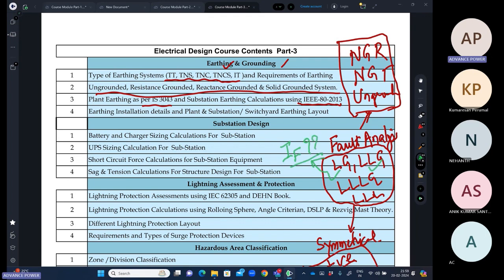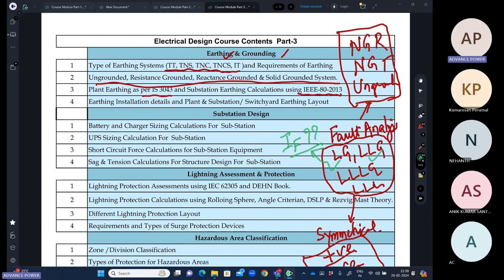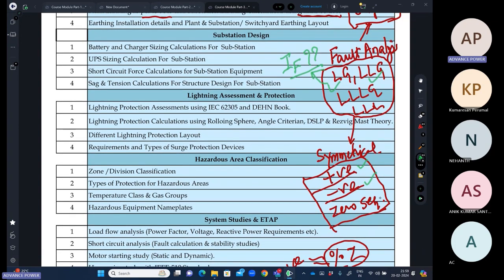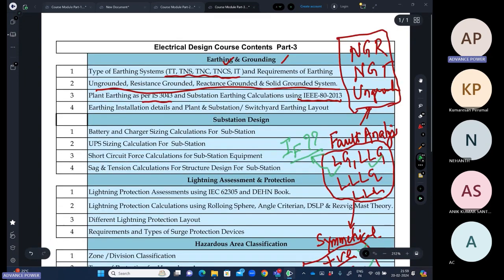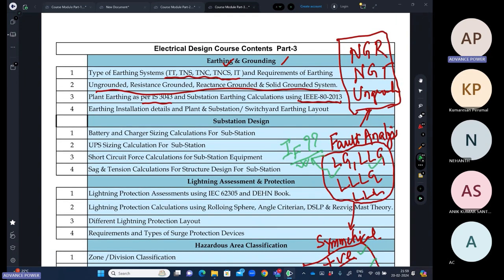Also, we'll see the voltage level in different substations. As per the voltage level, the CEA has defined the short circuit parameters to be maintained. Sometimes we take those values as well. And when all these component resistances and reactances are available, then we can easily calculate the fault current in our system.